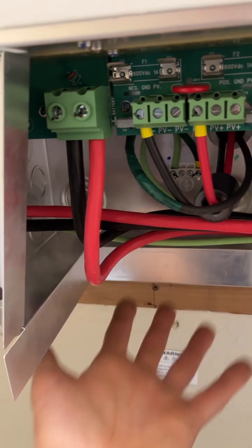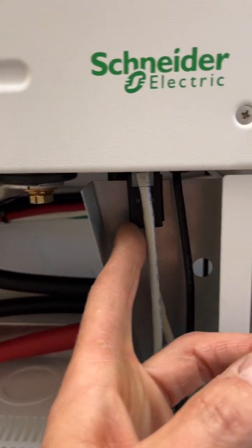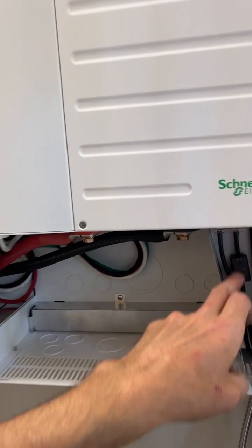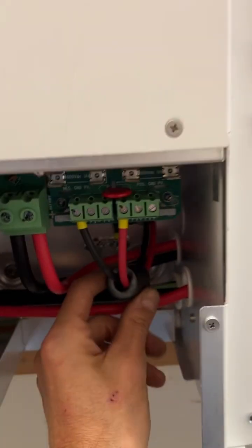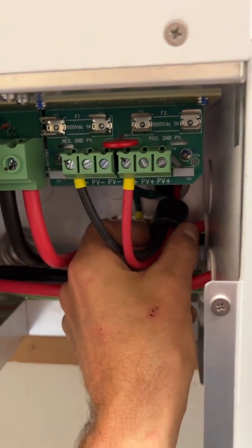So much wire, it was really hard to work with. All in all, now my bottom trays are going to sit down here. My isolations down here, they don't give ferrites for the Xanbus. They give them for the inverters, they came with the inverters. They did not come with the charge controllers. I don't know if the charge controller should have them or shouldn't have them. They're not inverting, they're just converting the DC from high voltage down. These are inverting, there might be a high frequency effect and that's what these will help block. On the charge controller they get the high frequency protection with their ferrite, and it cleans up the signal so you don't get any interference on that line.